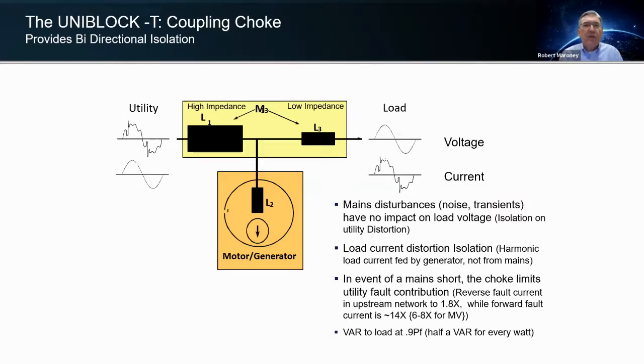For example, this choke would take a 50% current harmonic from your load and take it down to less than 3% on the input of the UPS. And as you know, current harmonics going back upstream to your utility or your infrastructure cause problems. It also provides difficulties for power generation equipment, generator sets, to voltage regulate. If you have a high harmonic load that's being allowed to propagate back towards the generator set, it actually can keep the generator from being able to voltage regulate and come up to speed. As you'll also notice today, there are no filters on these systems because of this choke.